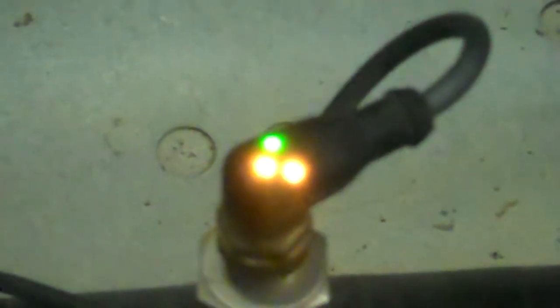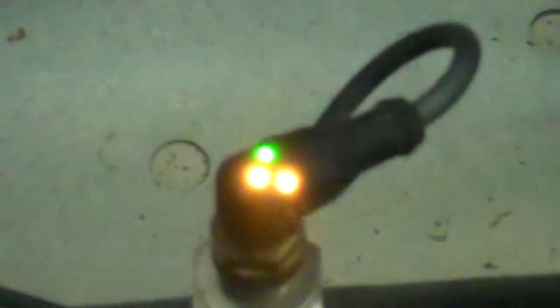FYI, there is a GFCI outlet here, an accessory. Again, you can see our four compressors in here, our brazed plate heat exchanger. And one of the things I want to document here right now is our flow sensor. This has an electronic flow sensor. It's got three lights on it. Right now, the green means power is on to it. When you see the two yellow lights, that means you have flow. It's sending a signal back to the controller that you have sufficient flow.